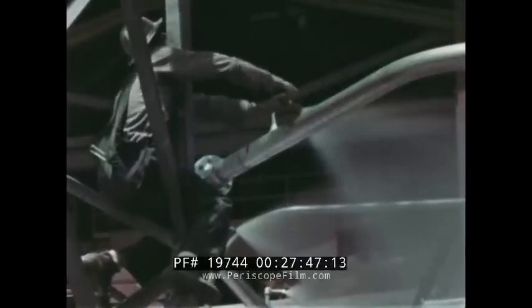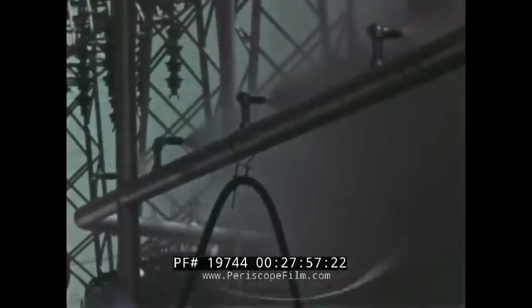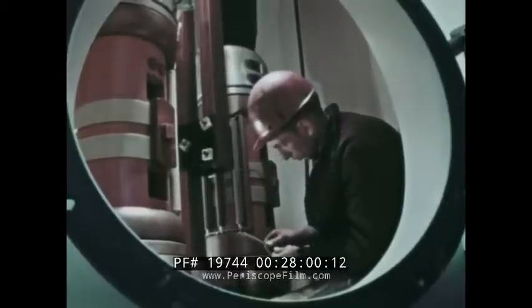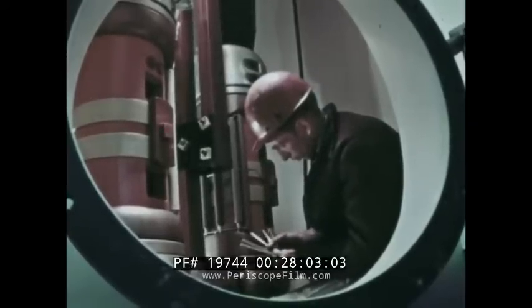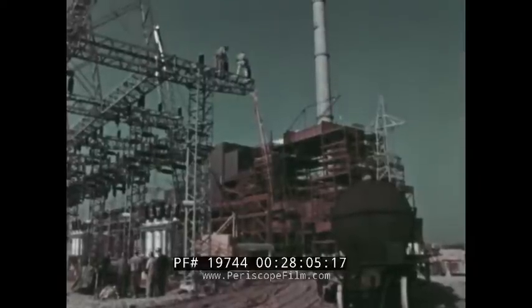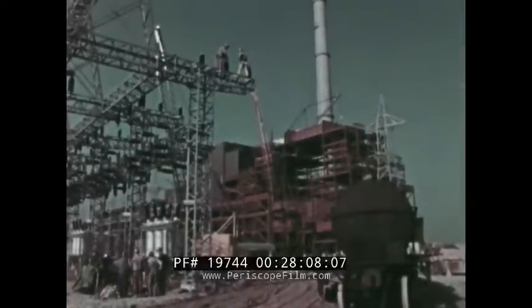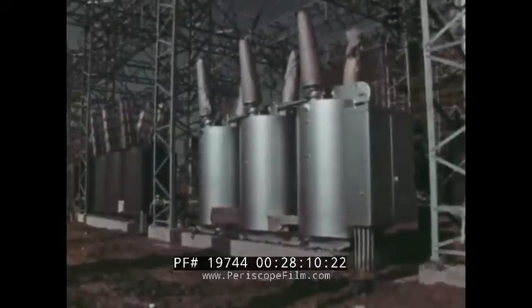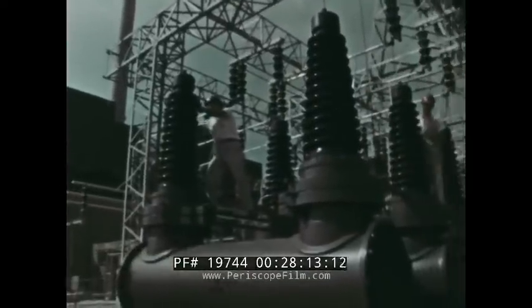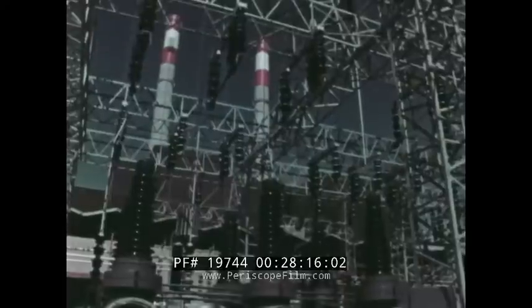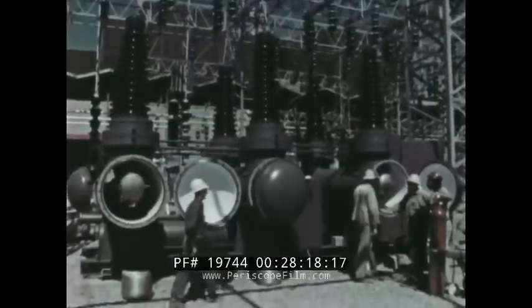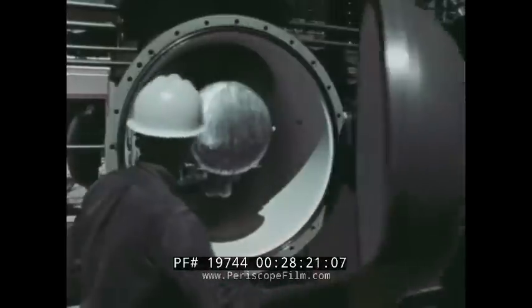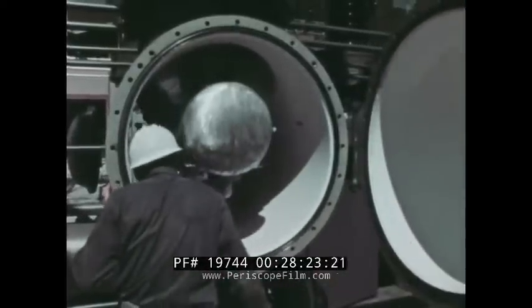Electrical trouble inside the transformers and even hot weather outside can threaten difficulties. In case of fire, an automatic water spray provides protection. The large generators at Paradise required the development of special 161,000-volt power circuit breakers. These are the safety devices guarding against great unexpected surges of power that might be caused by equipment failure, lightning, or other accident. Both oil and gas circuit breakers are used. They can interrupt a short-circuit current in less than a 20th of a second.